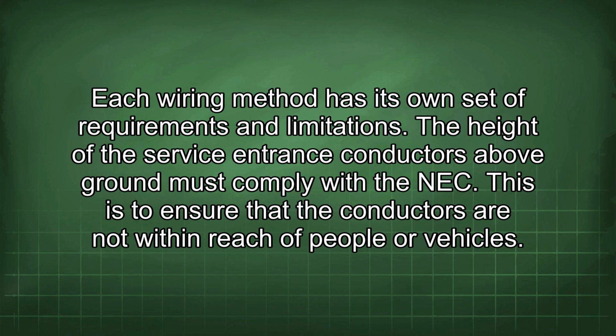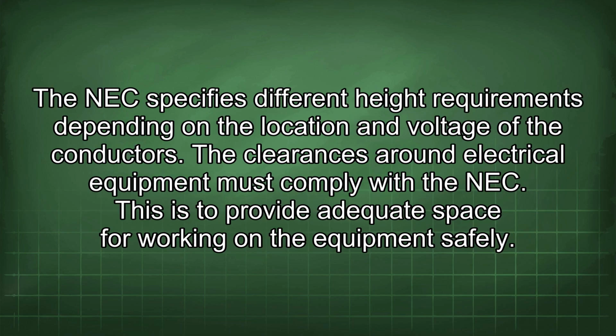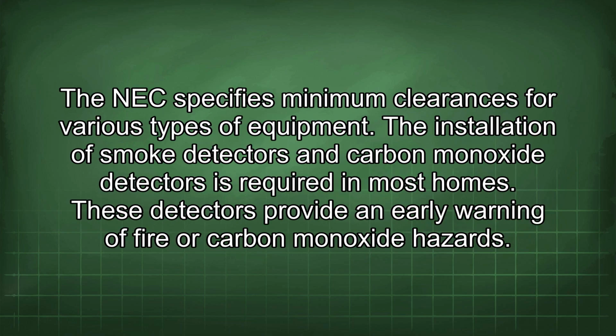The height of the service entrance conductors above ground must comply with the NEC. This is to ensure that the conductors are not within reach of people or vehicles. The NEC specifies different height requirements depending on the location and voltage of the conductors. The clearances around electrical equipment must comply with the NEC. This is to provide adequate space for working on the equipment safely. The NEC specifies minimum clearances for various types of equipment.